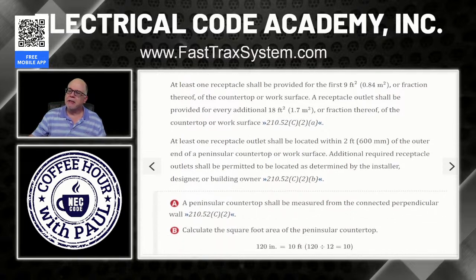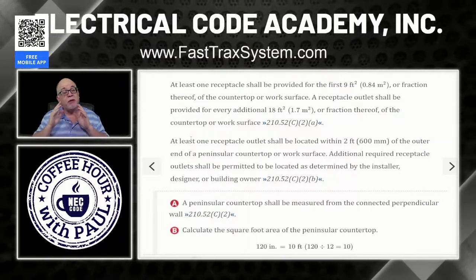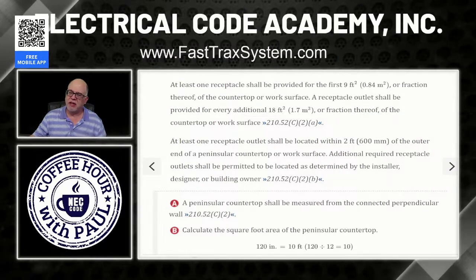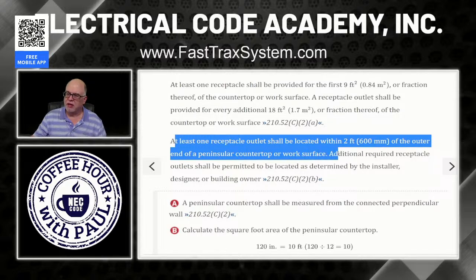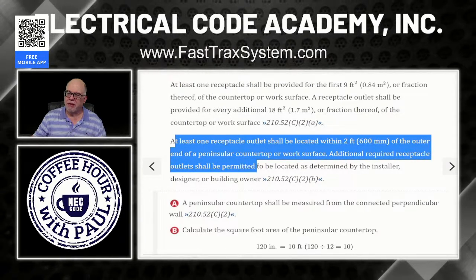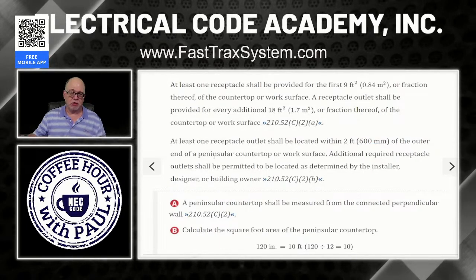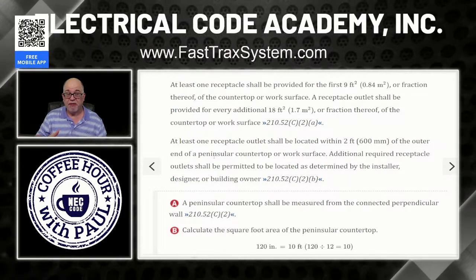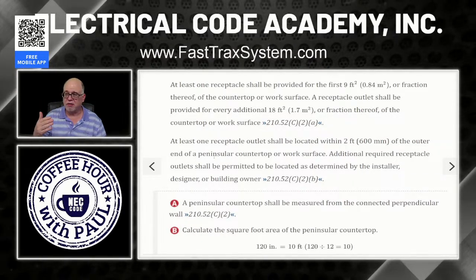Now, when it comes to a peninsula, that rule still applies, whether it's an island or a peninsula. But when the peninsula is involved, it says at least one receptacle outlet shall be located within 2 feet of the outside edge of the peninsular countertop or work surface. Additional required receptacle outlets shall be permitted to be located as determined by the installer, designer, or the building owner.